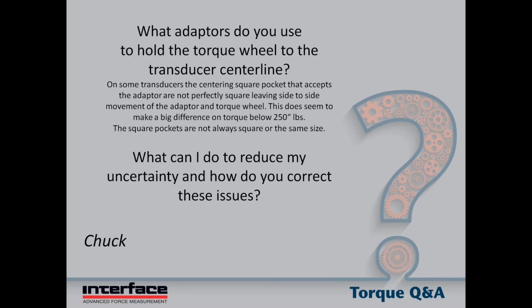Moving on: what adapters do you use to hold the torque wheel to the transducer center line? This is a tough one, so I'm not sure exactly what is meant by the torque wheel, but I can comment somewhat on square connections. Just as we talked about with shrink disc type couplings that apply a torsion uniformly around the sensor shaft, versus a key that applies a point load at the key, unless it's an interference fit, but just a slip fit with the key, the torque is actually applied as a force at the keyway. On square fittings, you have the same issue, except the squares are typically quite a bit sloppier than a hub sliding onto a shaft, and you have potentially 4 points of engagement that may move around as the torque is applied, even in a system that fits well, as things bend and mate together with increasing torque. So even the best square connection is less than ideal.